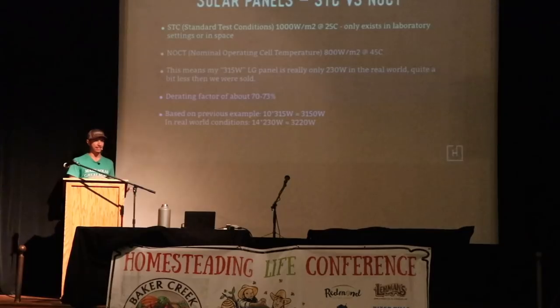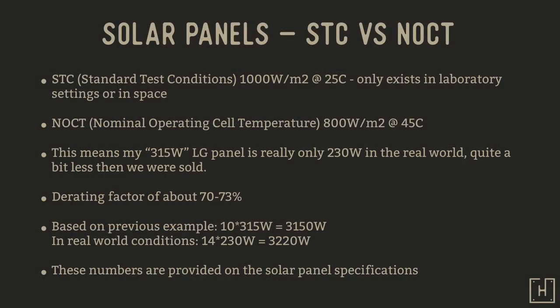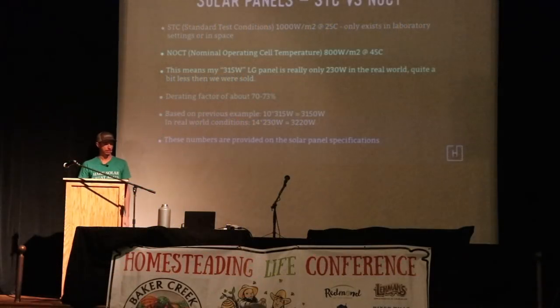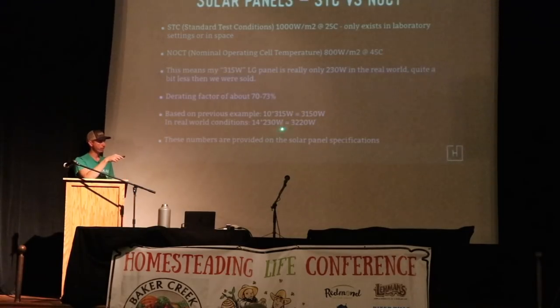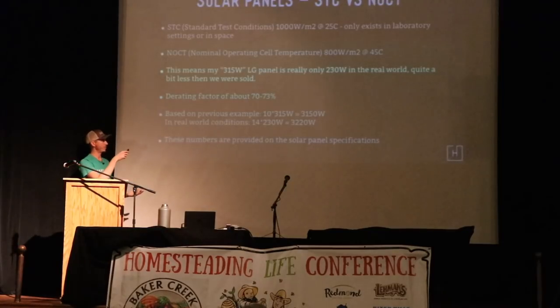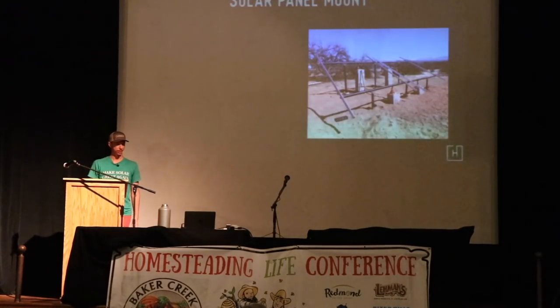Based on our previous example where we needed a 3 kilowatt system, if we take 10 of these LG panels and multiply by 315 watts, we'd think we only need 10 panels to get over that 3.08 kilowatts. Realistically, we're actually going to need 14 panels. All these numbers are provided on the solar panel specs. If you look at the specs, it gives you the STC number and also the NOCT number.